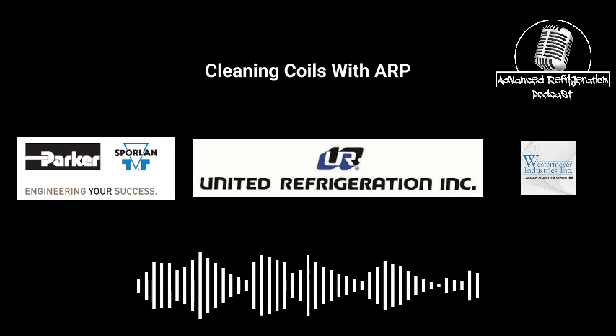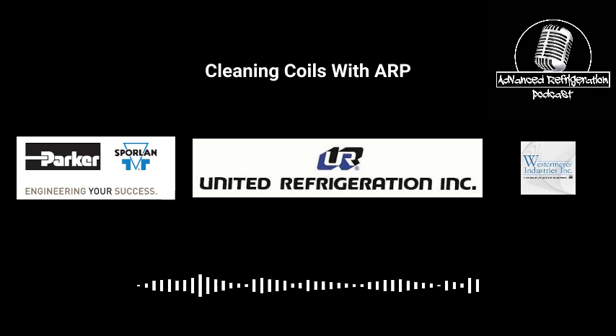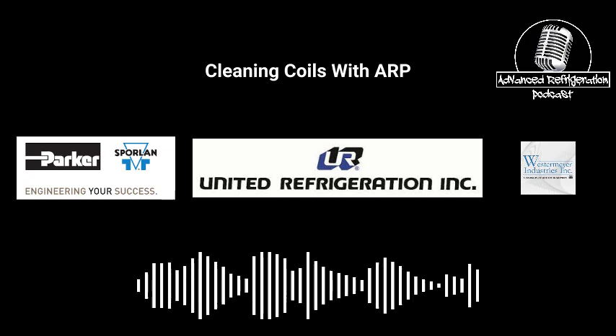It stops guys from putting a sprinkler on there. Before you put a sprinkler on something, you should probably make sure it doesn't have non-condensables or that the condensers run at peak efficiency. If it's blowing out the sides, it's impacted. It needs cleaned, and it needs cleaned properly.